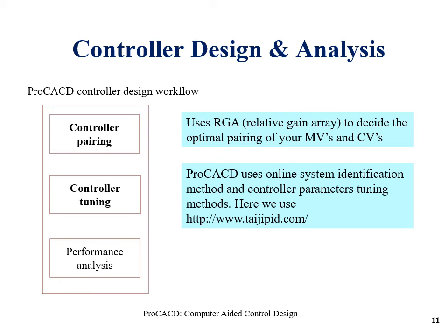The second most important thing is the controller tuning. Here ProCACD uses an online method. First, we generate the system response data by giving a step input on all the different available manipulated variables. We record the response of the system in the form of the change in CV and how much time it took to go to a new steady state.